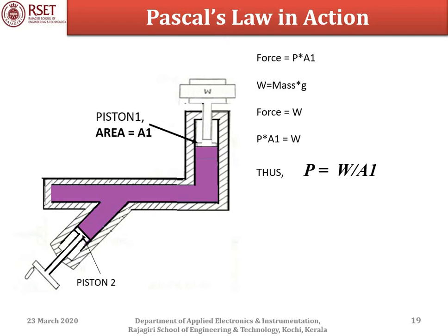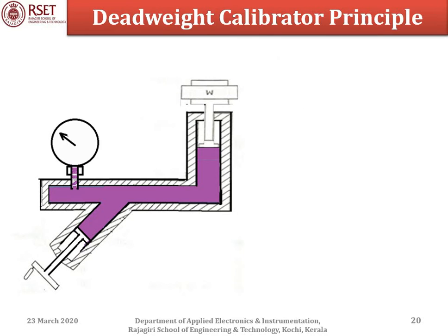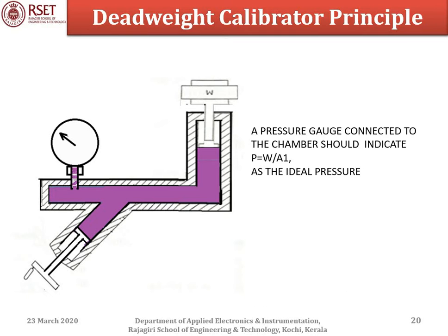Since W and A1 are known with very high accuracy, the calculation of pressure P is also very accurate. This calculated value of P can then be used to compare the reading of a gauge connected to the chamber. Ideally, the gauge should indicate a pressure of W / A1. Any deviation from this ideal reading is considered an error in the gauge.